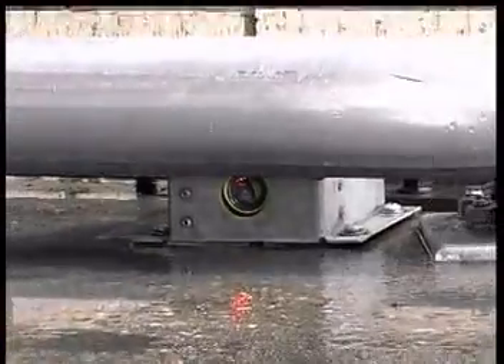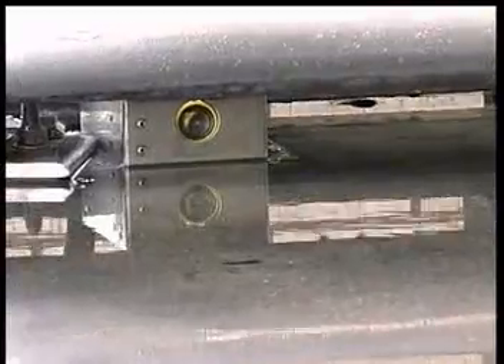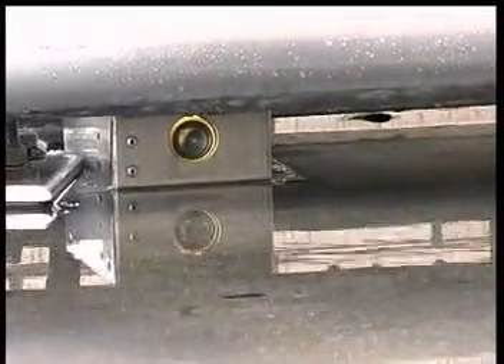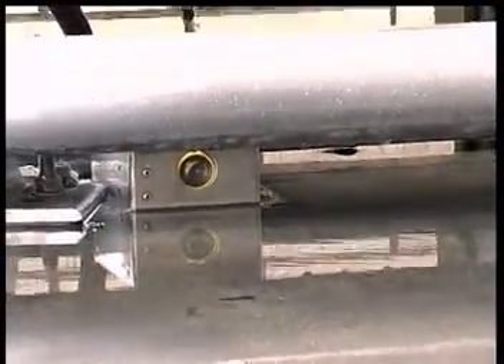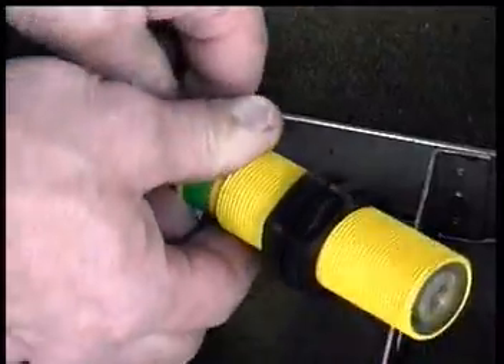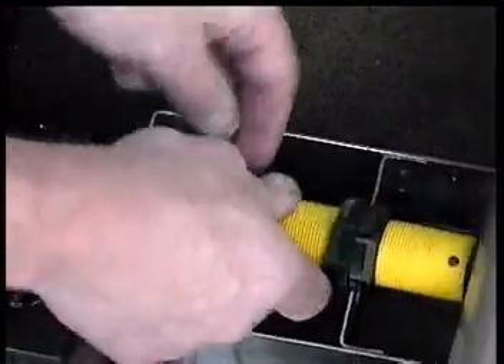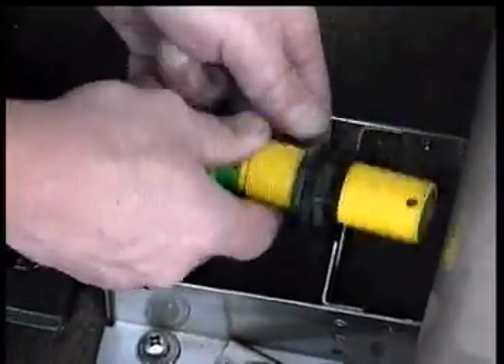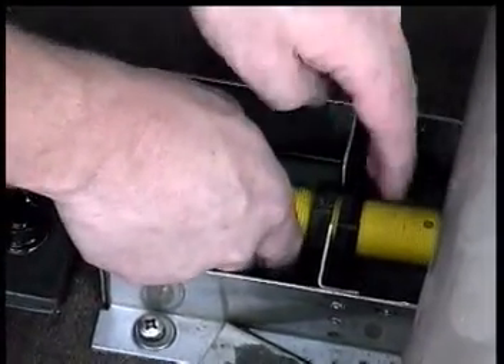If there is power on the transmitter, check for a red light on the receiver. Check the connections and for proper alignment. Screw-on connectors should be filled with electrical grease to keep out moisture. If connections are okay, replace receiver eye and recheck operation using service screen.